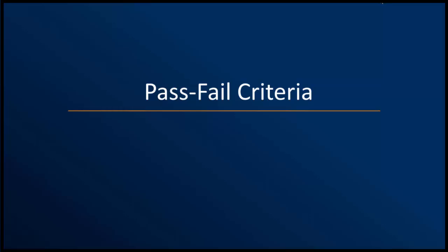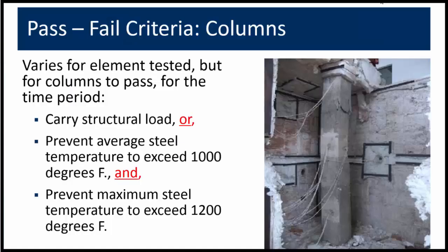We'll now review some of the typical pass-fail criteria for these major structural elements. For columns, the passing criteria is simply to carry the load for the desired time period while exposing it to the ASTM E119 fire curve in the furnace. Alternatively, if it can be demonstrated that the column steel temperatures do not exceed prescribed limits, then the column design can also be approved. The test standard provides detailed information about the number, location, and types of thermocouples used to measure the temperature of the steel within the column.